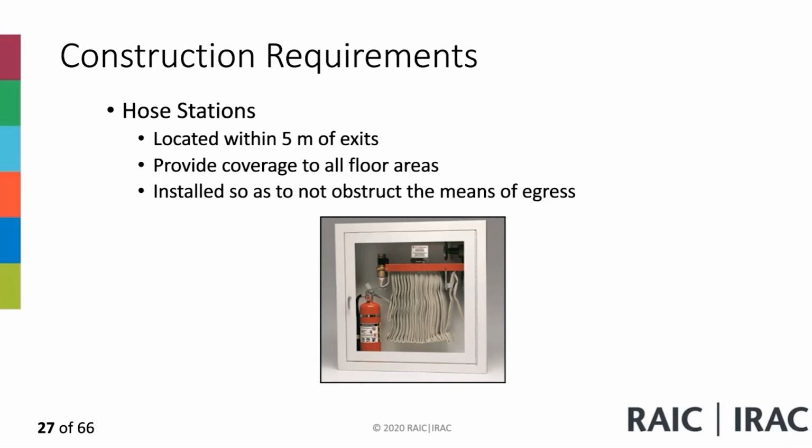That's another table you need to be familiar with, because putting in standpipes takes up space, and you need a lot of coordination with the mechanical engineer on the project. It's going to impact your stairs, your shafts. If you are required to have a standpipe system, double check the provision of 3.2.5.8, and it tells you those requirements.